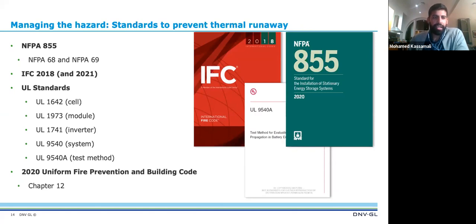UL has provided a series of certifications, testings, and standards you could adhere to in order to ensure your energy storage system is safe, specifically a lithium ion energy storage system. Starting at the cell level, UL 1642 is a series of tests and requirements that make sure the cell can tolerate certain abuse conditions such as overtemperature, overcurrent, undercurrent, and so on. The next one, UL 1973, covers the module or system level of multiple battery cells, with an added degree of testing and scrutiny since more components are involved.